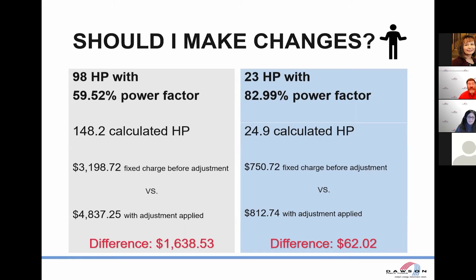You can see the two charges that he gets there before and after the adjustment. So this is an annual difference of $1,638. That's probably going to be worth it to put a new capacitor on and get that corrected, right? Now, let's say you're just a little 23 horse motor with about an 83% power factor. Well, that bumps you all the way from 23 to nearly 25. So your difference before and after the adjustment is only $62 a year.